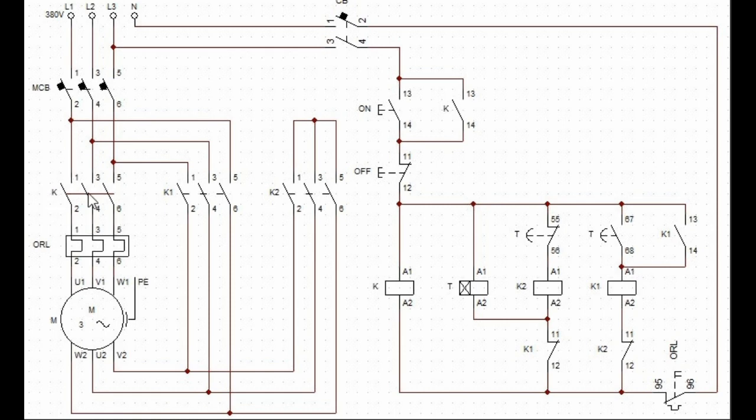From the output of contactor K, three phases are connected on the overload relay and then supplied to the motor terminals. L1 is connected to U1, L2 is connected to V1, and L3 is connected to W1.